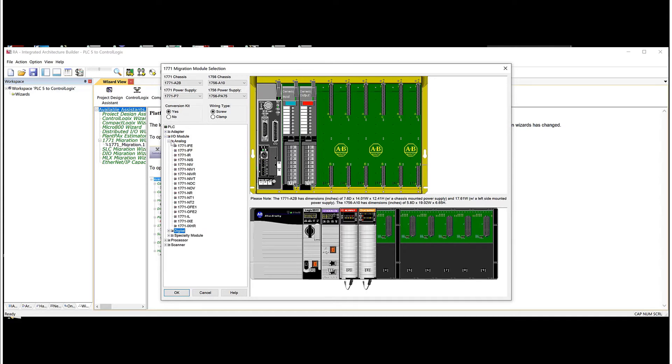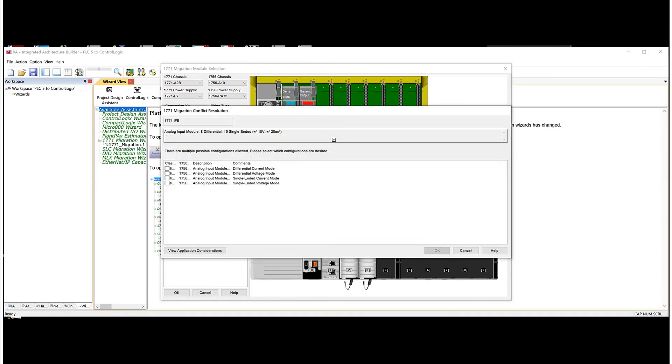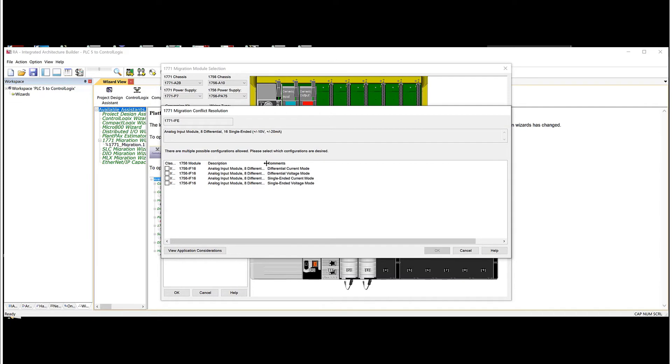Now let's just pick some analog cards. So we'll do an IFE. So I'll drag an analog input card in. And now here it's going, all right, well, we're going to use an IF16, but now we need to know are we using differential current, voltage or single ended current or voltage. I'm going to pick differential current.